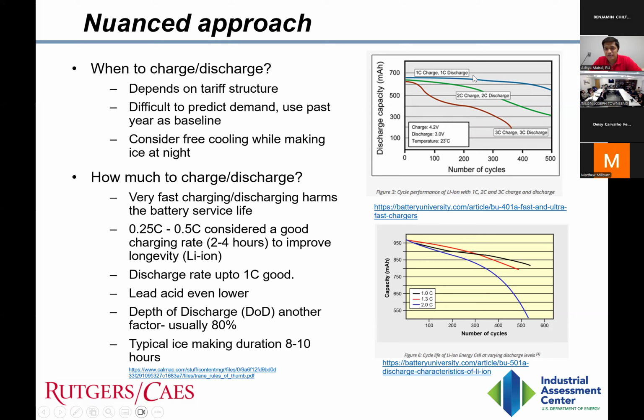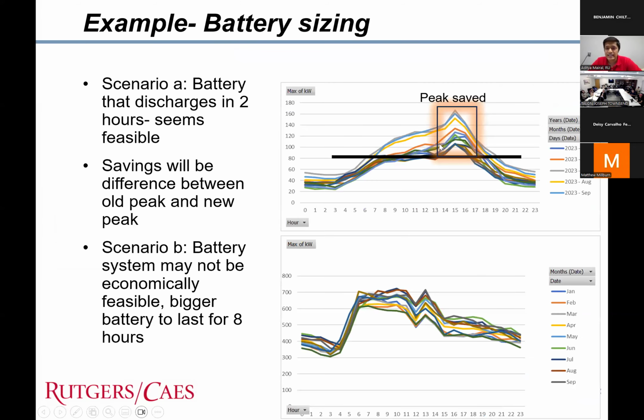So it's not recommended to do that a lot. There's a graph of C value versus the number of cycles the battery lasts. The idea is that a good thumb rule is 2 to 4 hours of charging and discharging time is necessary for a battery. Going back to this case, 2 hours here is perfect, it's ideal, and it can discharge over 8 hours. That's fine, but we need time here for it to discharge.